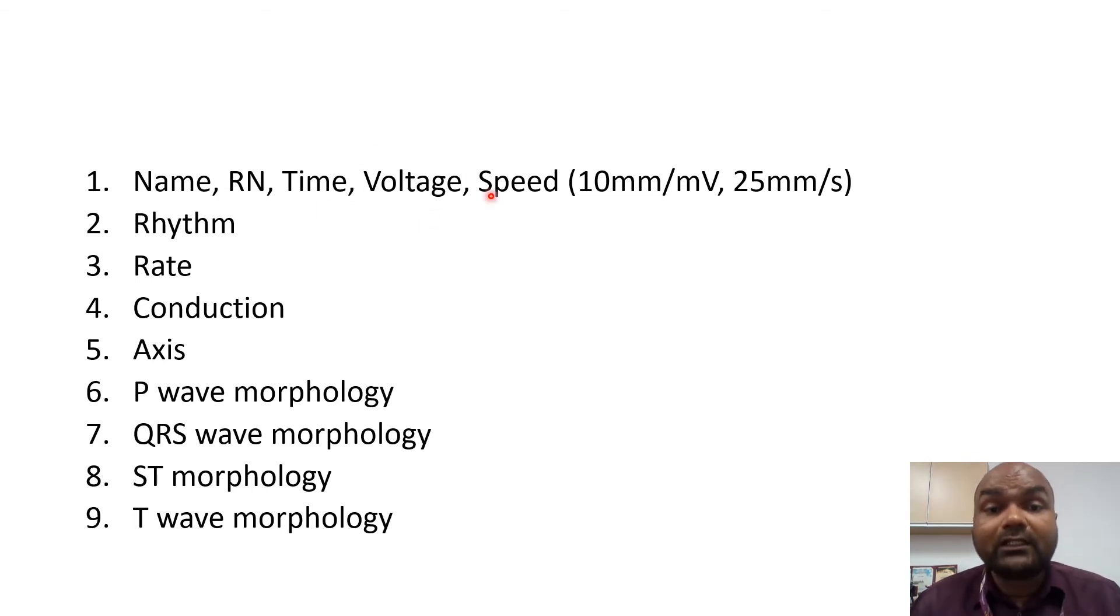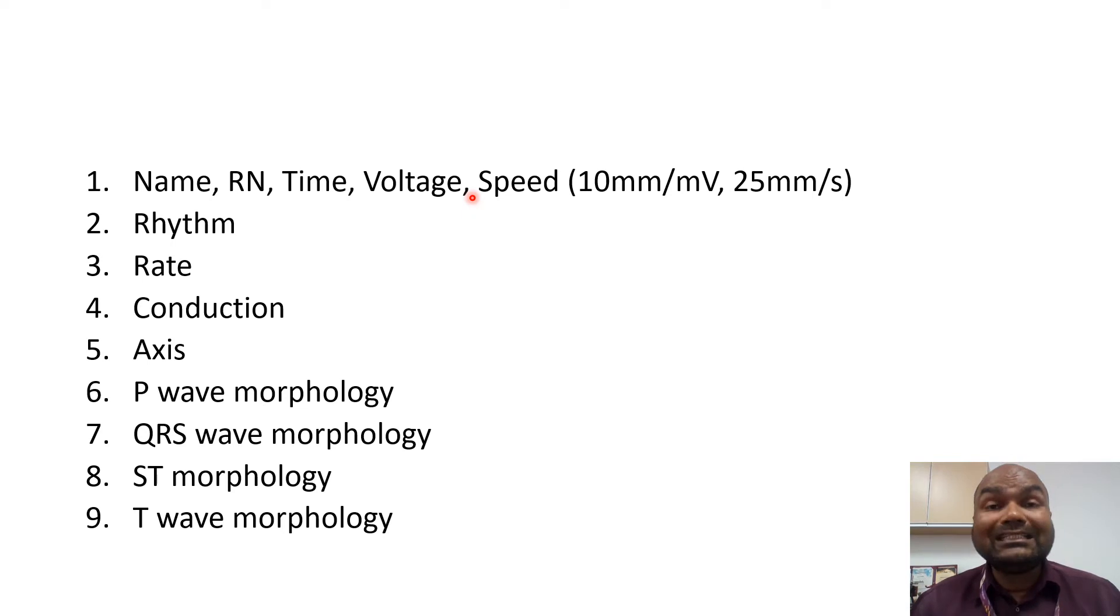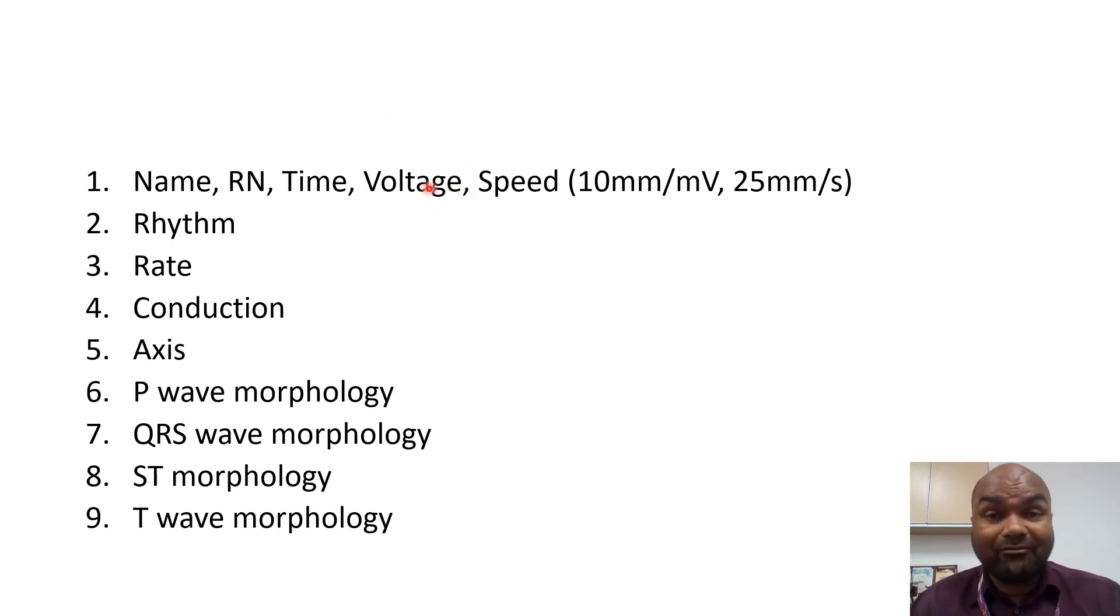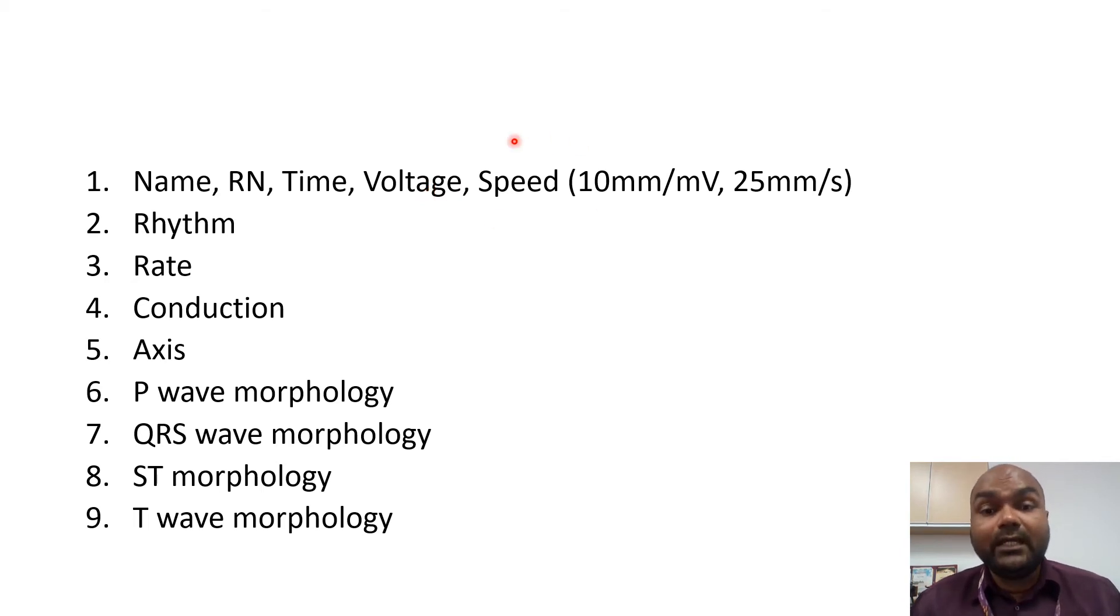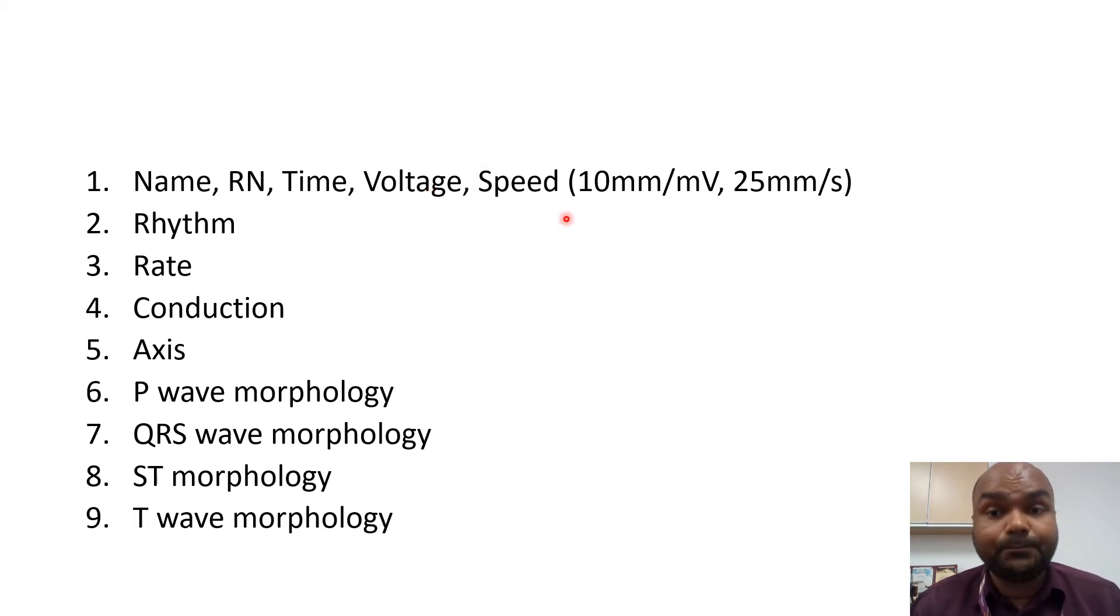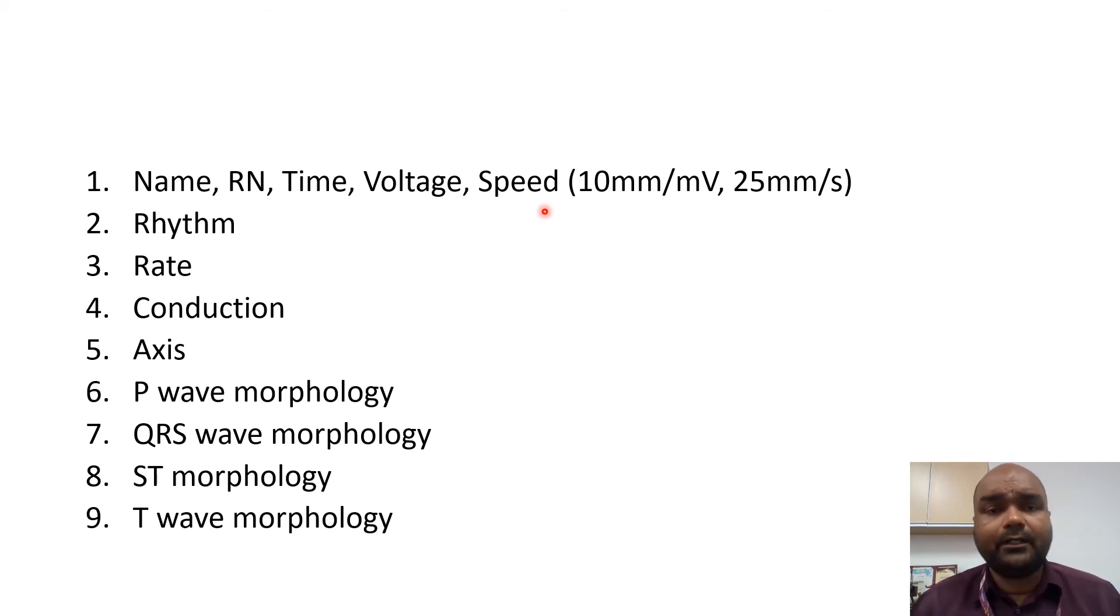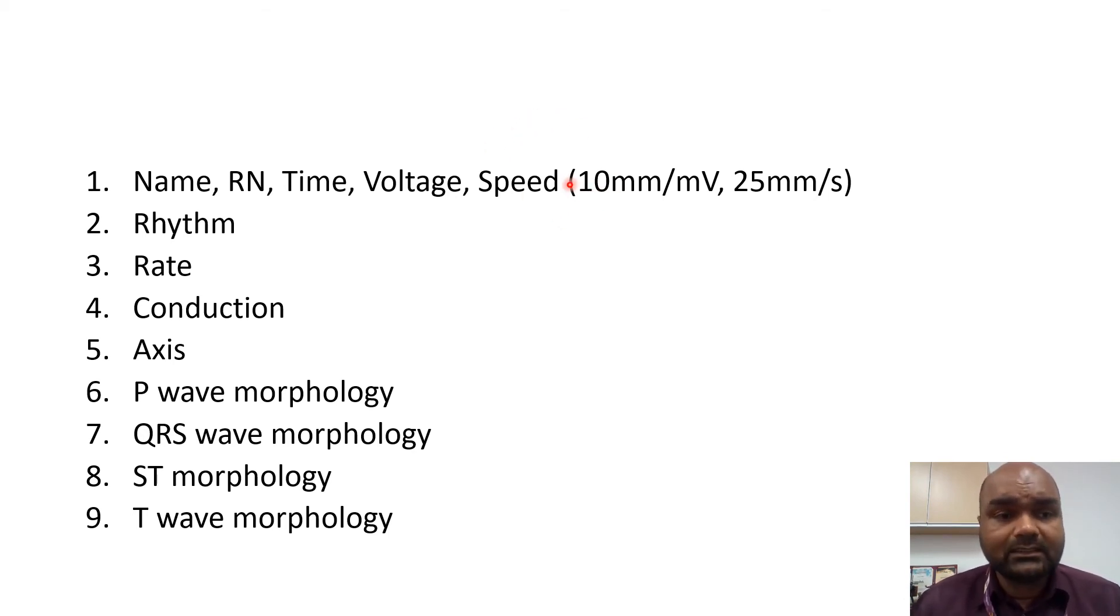Next you need to make sure that the voltage, the amplitude of the ECG is a standard amplitude, which is 1 millivolt for every 10 millimeters. So please check that first. Next, make sure the speed is a standard speed, which is 25 millimeters per second.